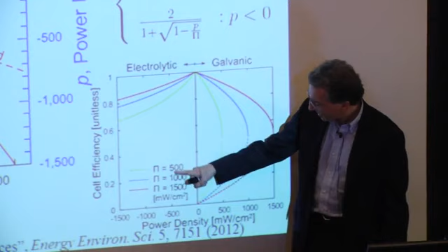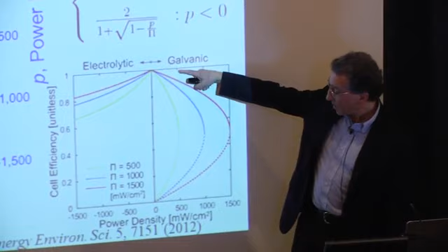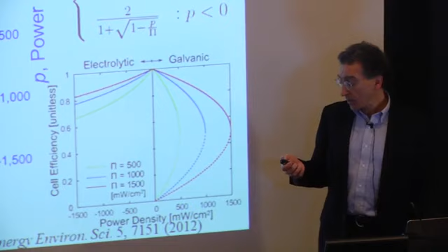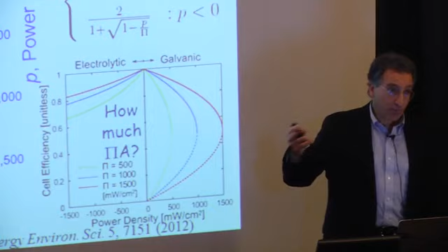And depending on the peak power density, if we go from 500 to 1,000 to 1,500 milliwatts per square centimeter, say at a given power density, the efficiency goes up and up and up. So we want more efficiency, we want more peak power density, right, or more area. But both of those things can cost you. And so the question is, how much peak power do you need to buy in order to get the efficiency up so high enough that you meet your overall spec round-trip efficiency for the system?